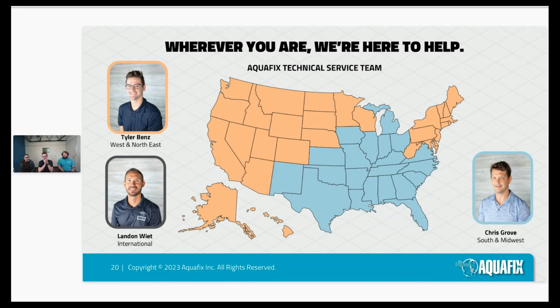And the same can be said too, I wanted to bring this up, if you have had to reseed your activated sludge plant, always be sure to do a microanalysis on that seed sludge before you add it into your system, because we've seen quite a number of instances where a municipality has gotten seed sludge either from an industry or another municipality down the road, and it's been chock full of Nocardia. And certainly that's another way to introduce the filament in there. So just be cautious with that.